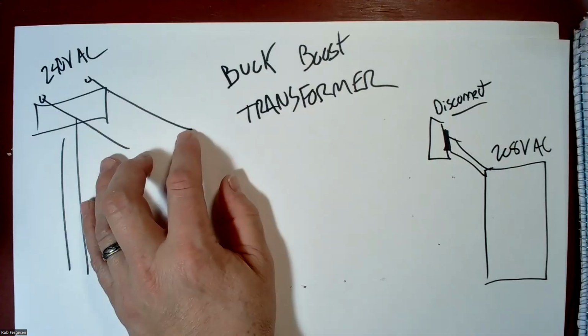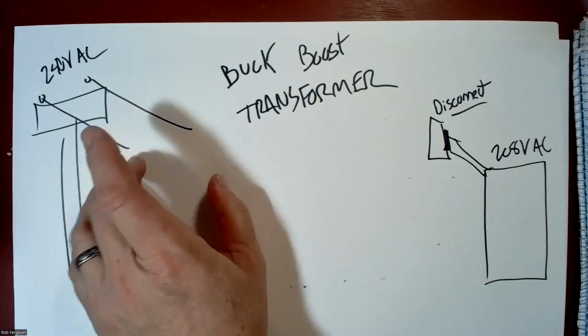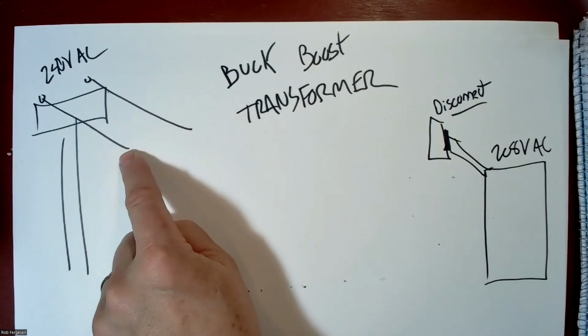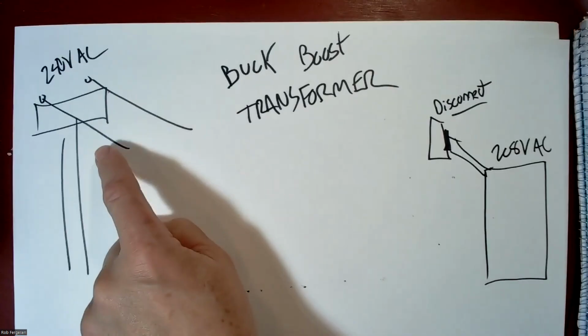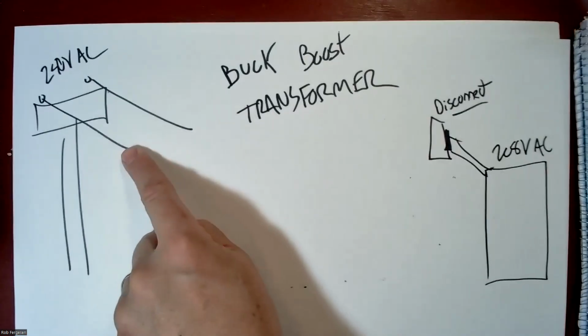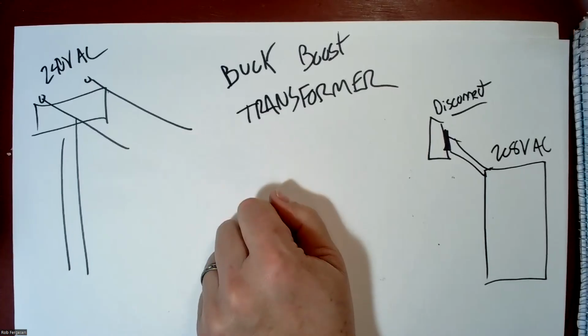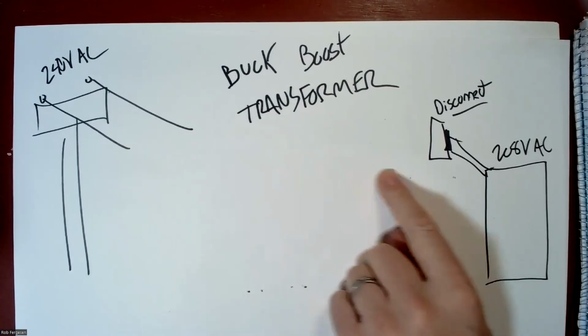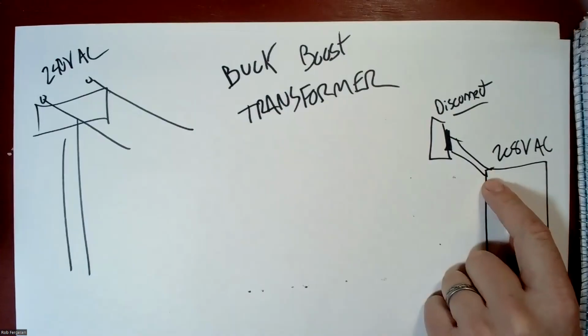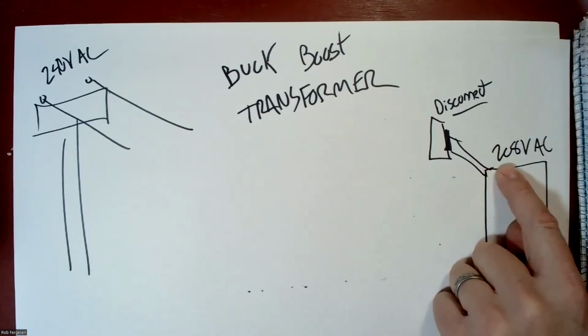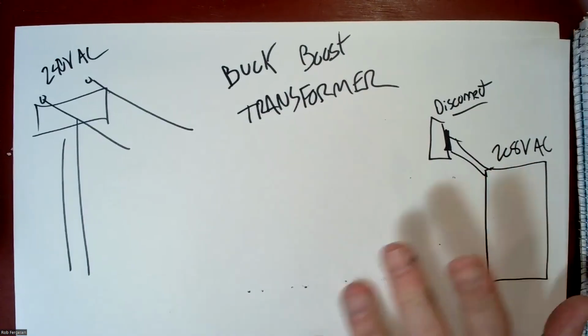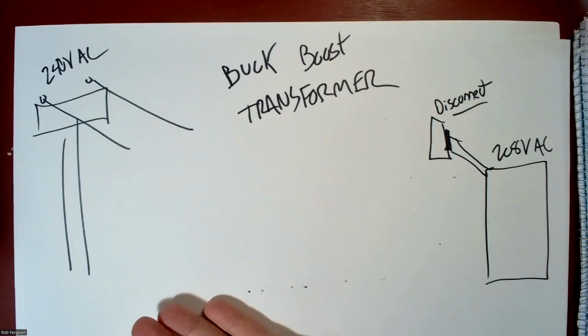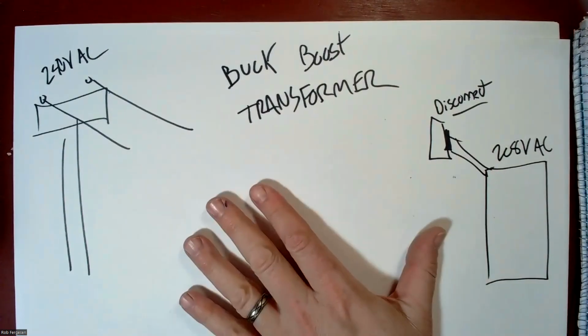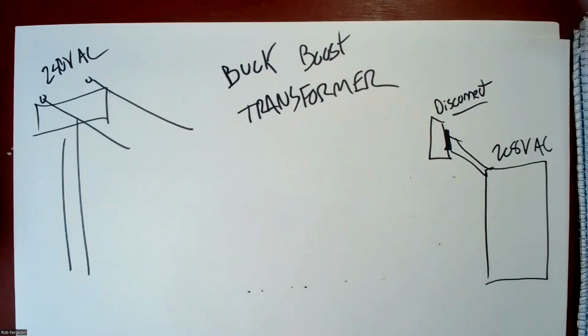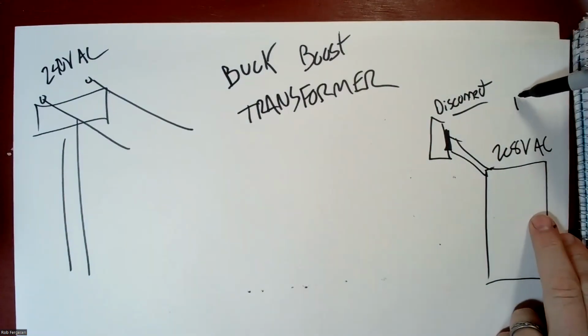If you remember, single phase 240, each wire is hot, but they're slightly off phase from each other. So the differential between this leg and this leg is 240 volts. But my grinder needs a differential of power going in of 208 volts. Generally speaking, you're allowed to have up to a 10% differential. So a 10% differential is okay.